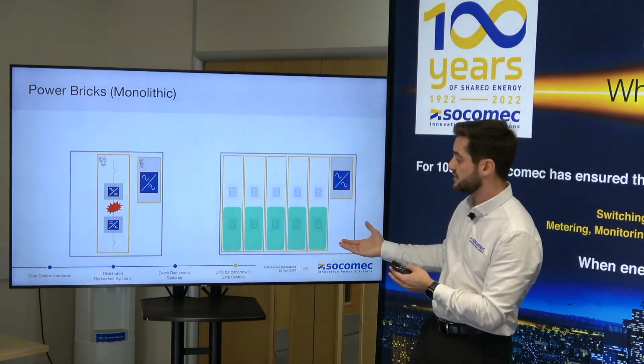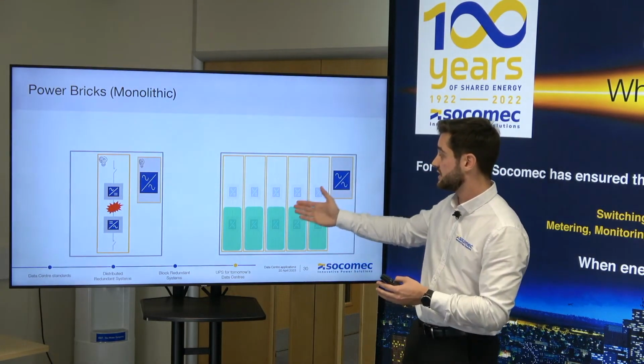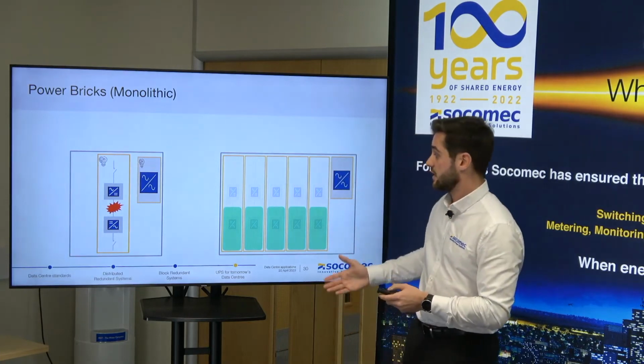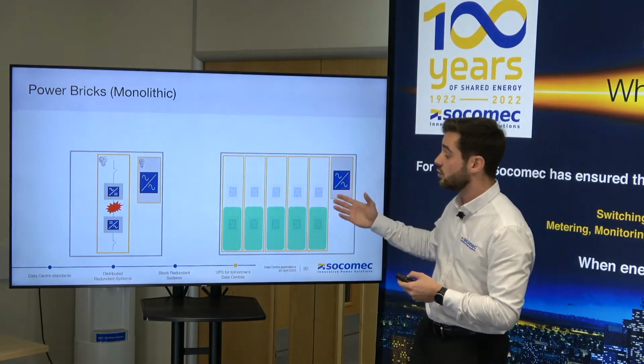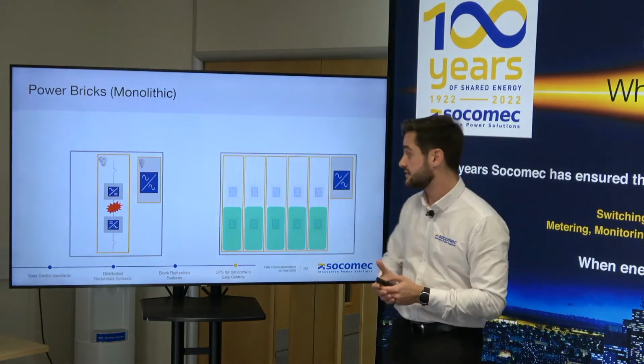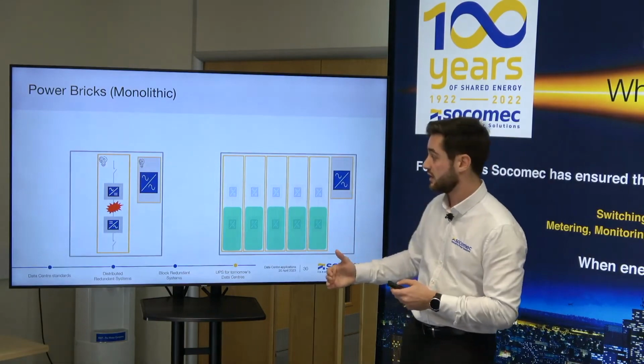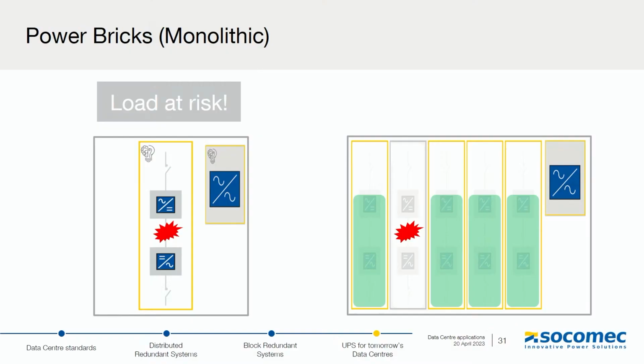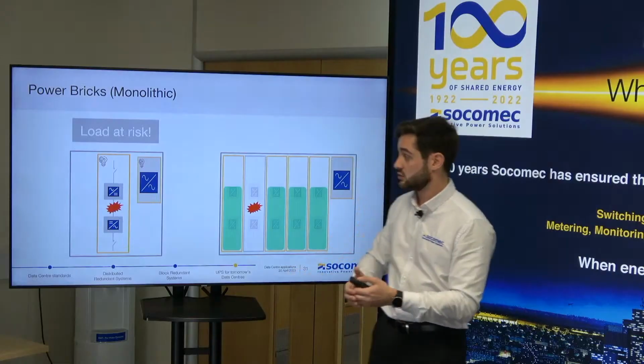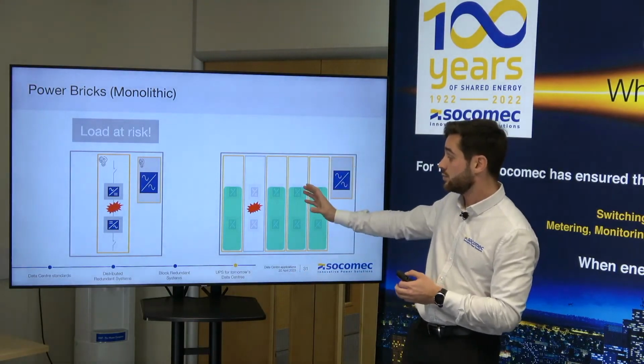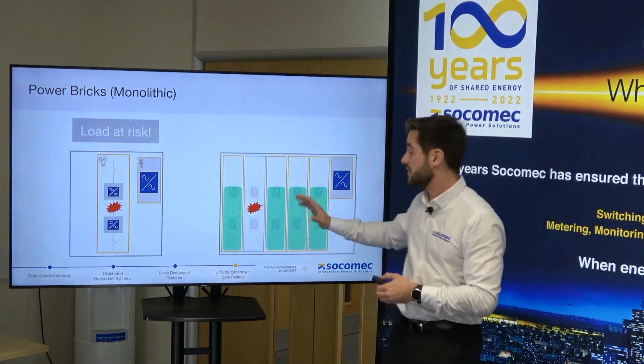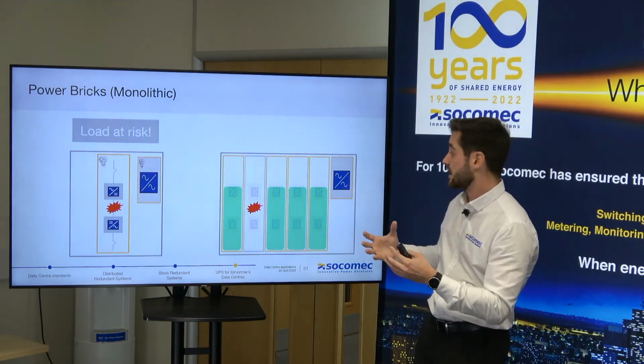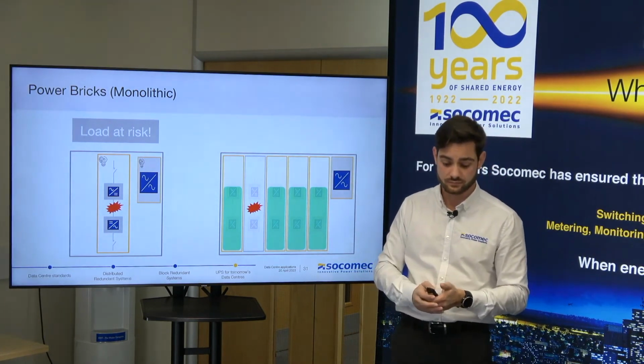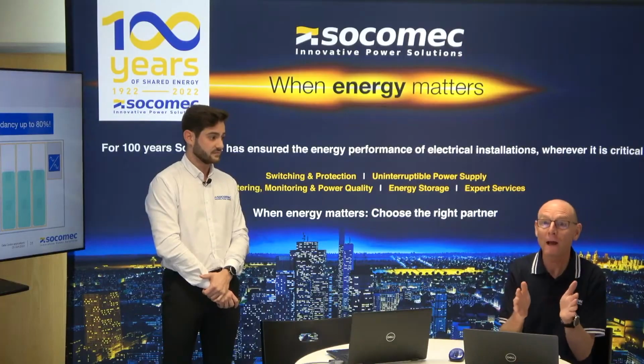We can imagine this one is, for example, 1.2 megawatts, and each power brick is rated at 240 kilowatts. The benefit is that if you've got a failure on one power brick, it wouldn't impact the overall system, as long as it can cover the load, of course. On a traditional UPS system, when you've got a failure, you need to switch on bypass or whatever. On a power bricks UPS system, if you've got a failure on a power brick, the other power bricks step up and take the load, and you don't have any problem. So what you're really getting is the benefit of a modular UPS, but in a monolithic. You've got the redundancy as you would have on a modular UPS, but in a monolithic UPS.